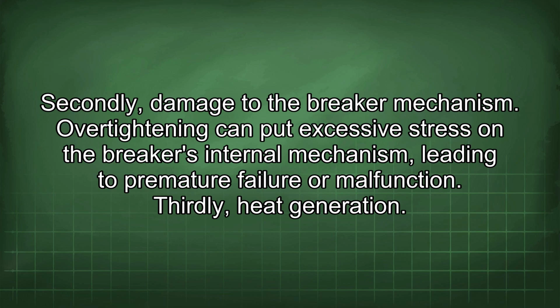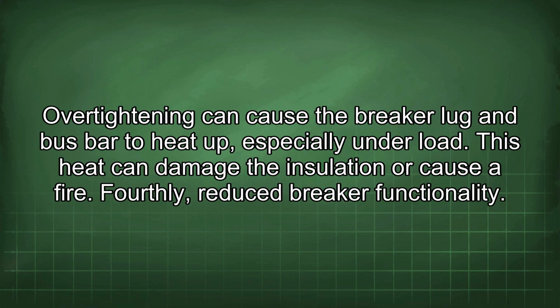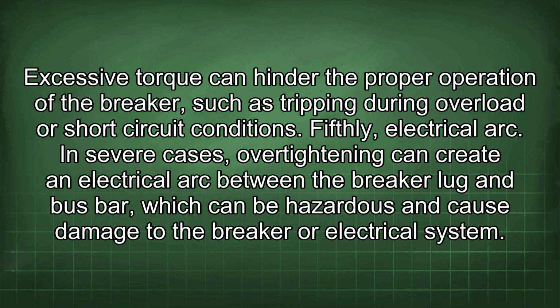Thirdly, heat generation. Over-tightening can cause the breaker lug and bus bar to heat up, especially under load. This heat can damage the insulation or cause a fire. Fourthly, reduced breaker functionality. Excessive torque can hinder the proper operation of the breaker, such as tripping during overload or short-circuit conditions. Fifthly, electrical arc. In severe cases, over-tightening can create an electrical arc between the breaker lug and bus bar, which can be hazardous and cause damage to the breaker or electrical system.